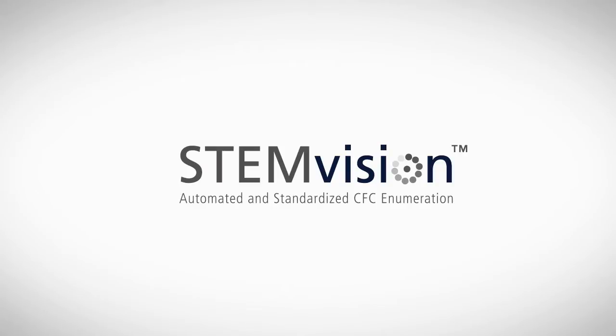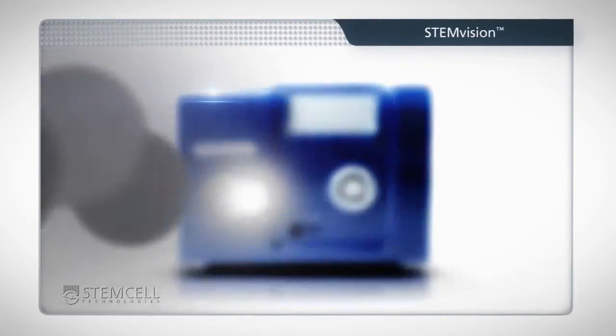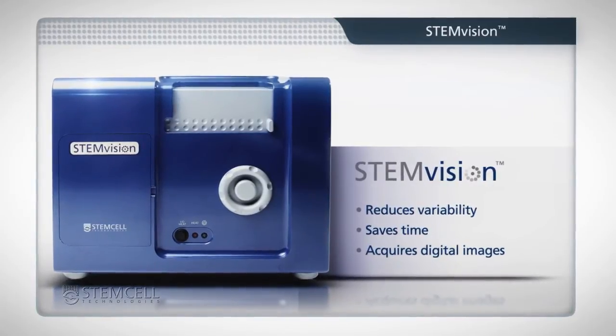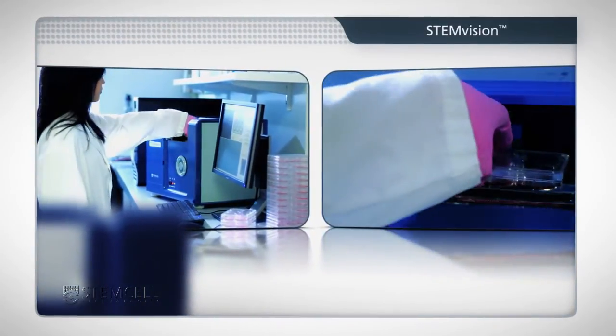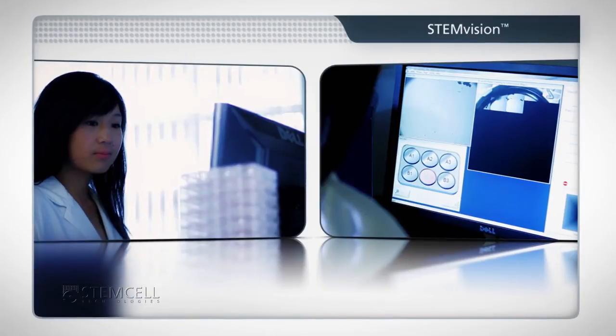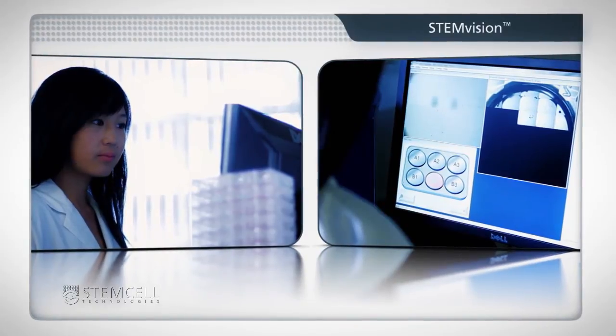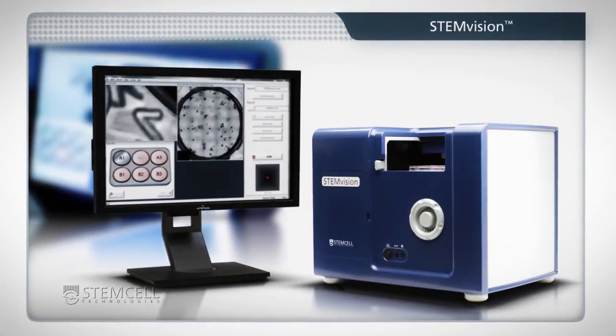StemVision is an automated instrument and computer system designed for imaging and scoring hematopoietic colonies in the colony forming cell, or CFC, assay. Developed by StemCell Technologies, StemVision reduces variability in CFC assay results, saves time, and acquires digital images for permanent record keeping. Instead of manually identifying and counting colonies using a microscope, users simply load cultures into StemVision. The instrument automatically images and analyzes cultures using highly sophisticated software and colony counting algorithms. StemVision is optimized for use with MethoCult media and the meniscus-reducing SmartDish culture ware.